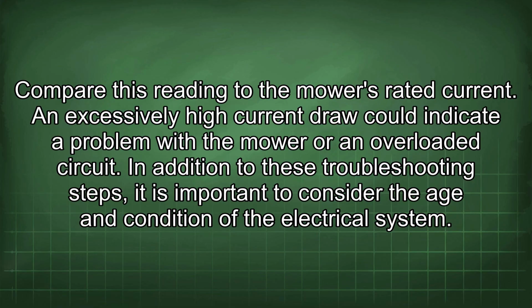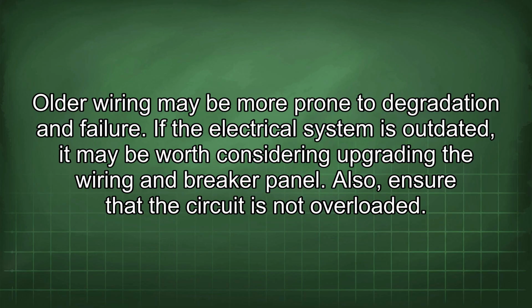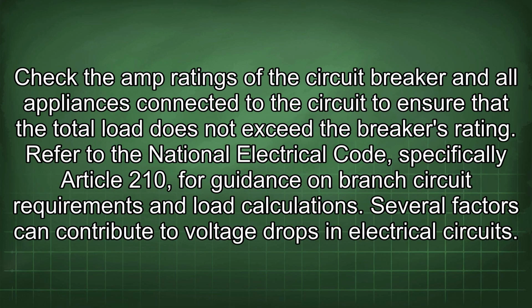In addition to these troubleshooting steps, it is important to consider the age and condition of the electrical system. Older wiring may be more prone to degradation and failure. If the electrical system is outdated, it may be worth considering upgrading the wiring and breaker panel. Also, ensure that the circuit is not overloaded. Check the amp ratings of the circuit breaker and all appliances connected to the circuit to ensure that the total load does not exceed the breaker's rating. Refer to the National Electrical Code, specifically Article 210, for guidance on branch circuit requirements and load calculations.